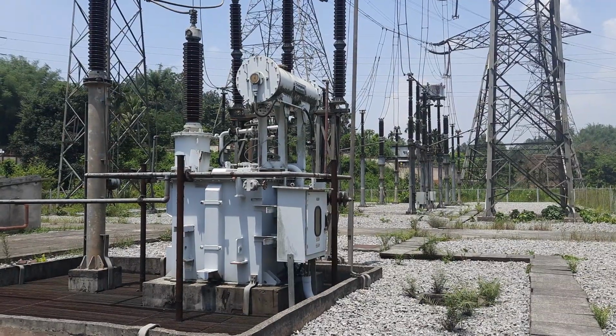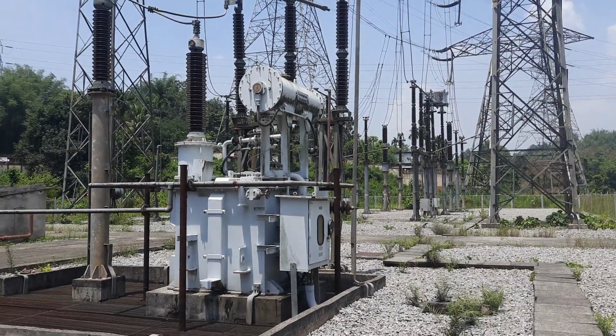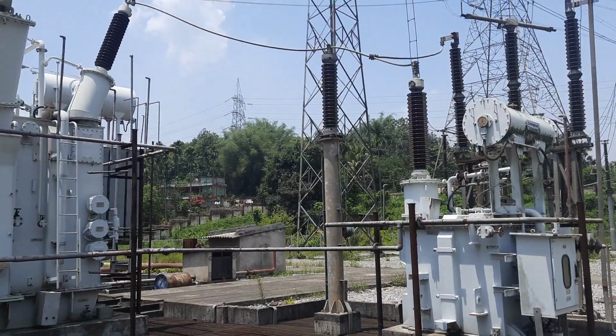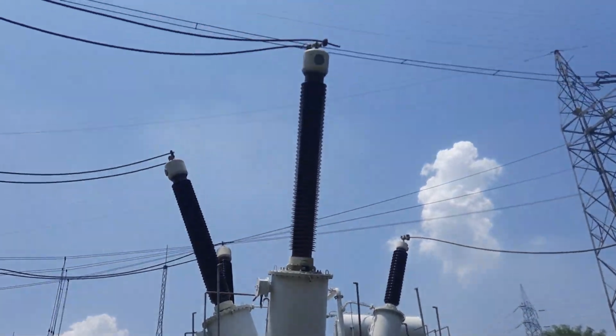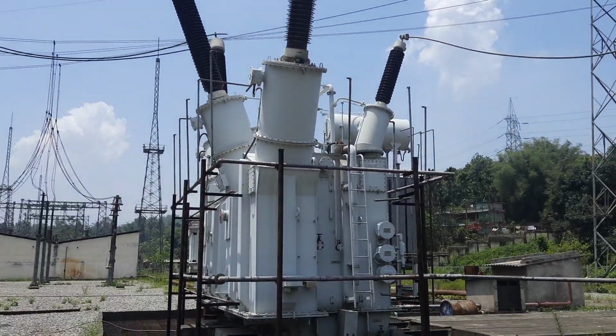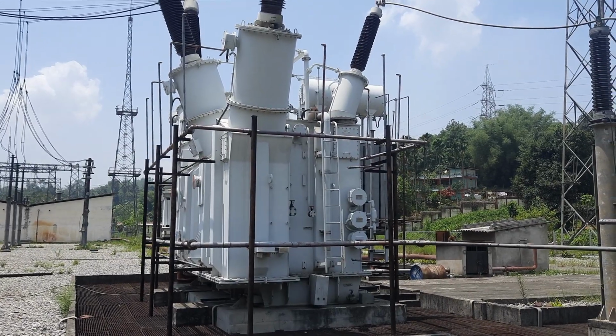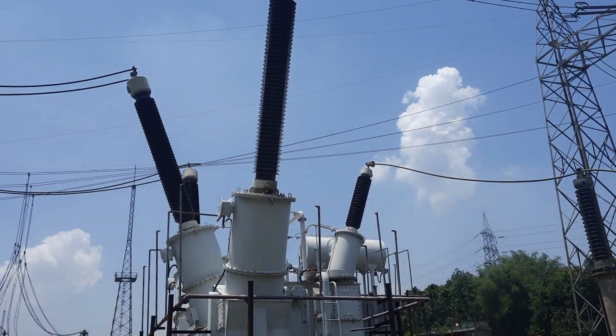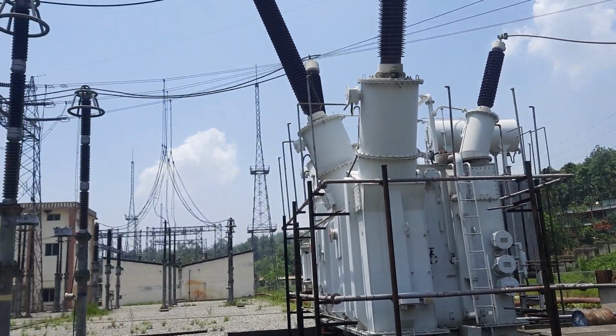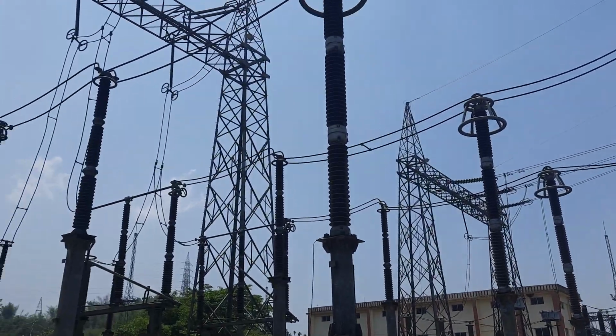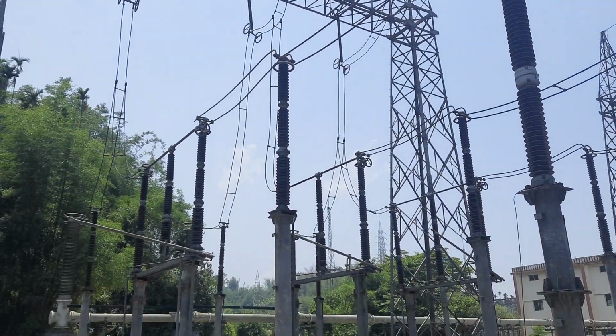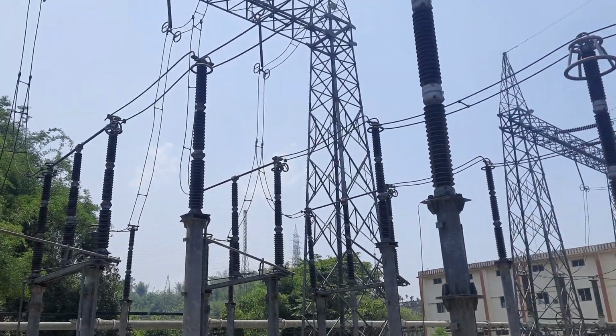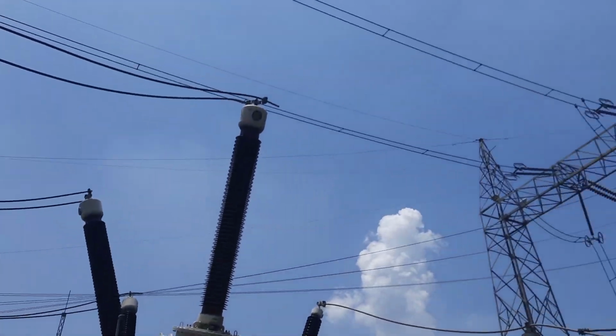Hello, this is the neutral grounding reactor, NGR, which is connected to the neutral of this reactor. This is our 50 MVAR reactor, a shunt reactor in fact. It is connected in parallel to this 400 kV line.